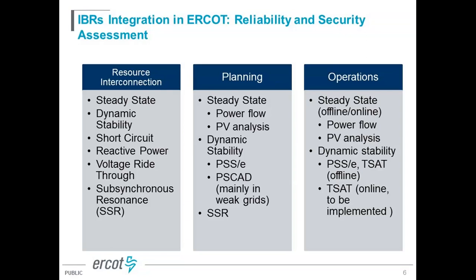So for IBRs connecting to ERCOT, at the interconnection process they are required to do the steady state, dynamic, and short circuit studies, which is very typical. In addition, they are required to perform reactive power studies to demonstrate that they can meet the 0.95 power factor requirements from their design perspective. They also need to show their capability to ride through disturbances for low voltage and high voltage. And because ERCOT has a series of capacitors in our system to facilitate the transfer capability, depending on the inverter-based technologies, if the resource connects to the series capacitors, they are required to perform the SSR, subsynchronous resonance, study. And this is where the PSCAD model is required for inverter-based resources to provide the model at the interconnection stage.